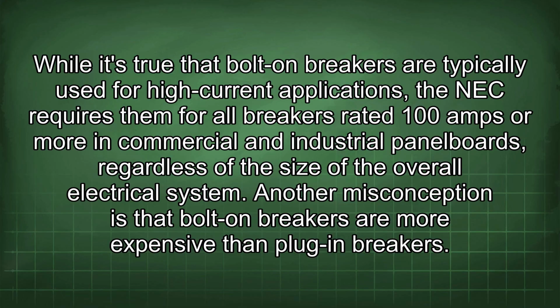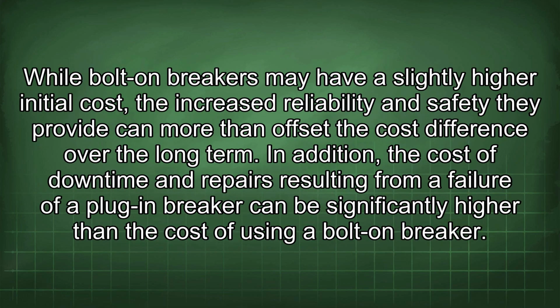Another misconception is that bolt-on breakers are more expensive than plug-in breakers. While bolt-on breakers may have a slightly higher initial cost, the increased reliability and safety they provide can more than offset the cost difference over the long term. In addition, the cost of downtime and repairs resulting from a failure of a plug-in breaker can be significantly higher than the cost of using a bolt-on breaker.